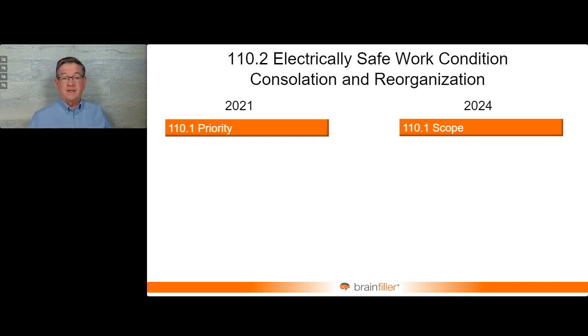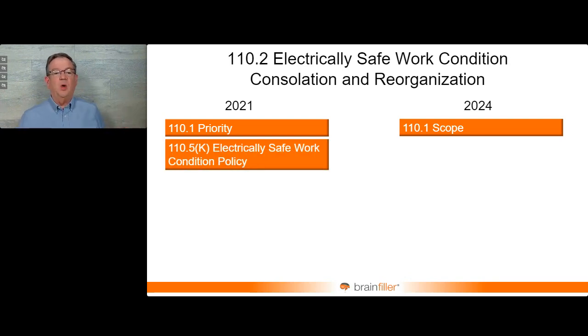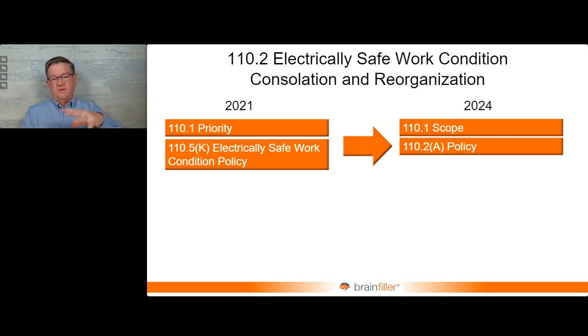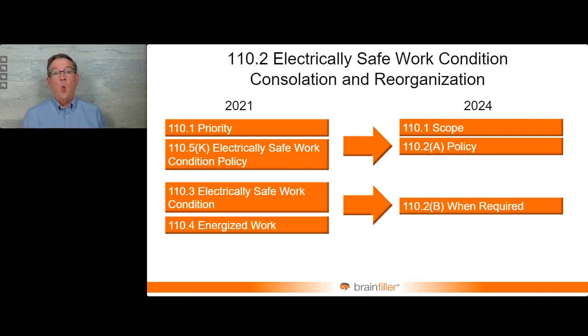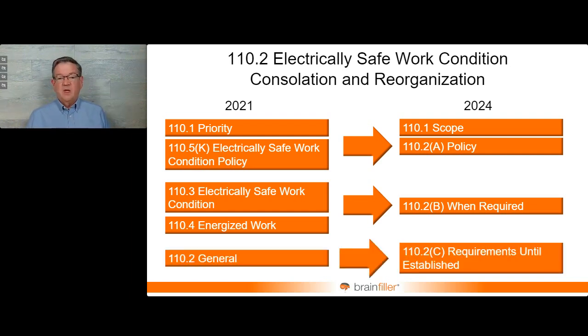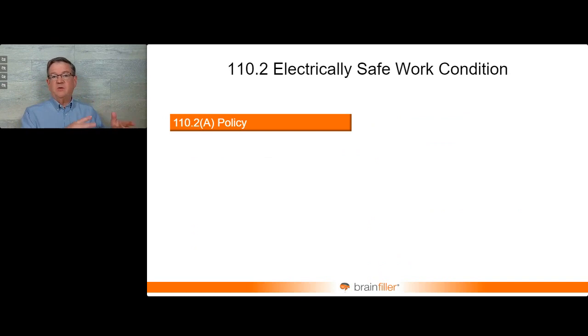And what happened is 110.1, which is priority, the single most important part of electrical safety, had to get moved around a little bit. And scope goes to 110.1. So we have the original priority, and we have the electrically safe work condition policy. Those were merged together, and they're just called policies. So everything falls into 110.2 now, this main part of it. In 110.2, we have A, the policy, and then these were brought together for B: when is it required? When is an electrically safe work condition required? So we have the policy, we have when it's required, and then we have requirements until you establish it. So a lot of the intent is still the same, some of the text is still the same, but there was a reorganization. Remember I said everything's in 110.2, so we have A.